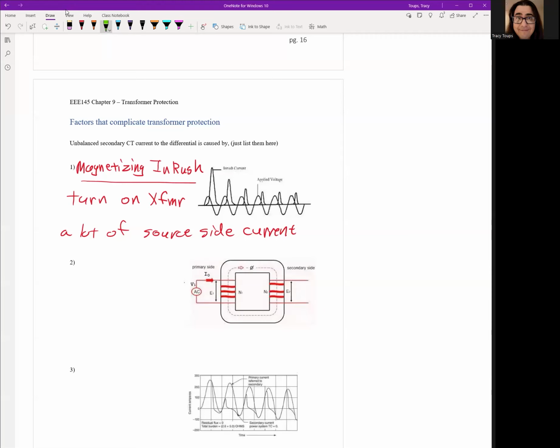The next one is going to be overexcitation. We talked about this a few other times, especially for the generator. Same thing here, right? We still have a lot of magnetic coils everywhere. You put voltage on, and if you have too much voltage applied, that's going to have some consequences. If you remember, when you have too much voltage, your magnetic field is too strong, and then you'll run out of the magnets inside the metal core to align, right? Those are called moments. So too much voltage, not enough metal, you can't turn the magnets anymore, and then what ends up happening is you pretty much distort the turns ratio.